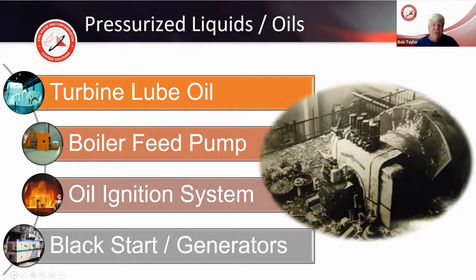Or they use it for the purpose of generating power or steam initially to do that. So pressurized liquids are very common in many industries. One of the factors is that when these fail, they are generally under pressure. The oil will become atomized, very fine particles, very quickly. If it hits an ignition source, that could be just a hot steam line, a steam pipe somewhere, it can be a devastating, fast-moving fire and a three-dimensional fire.